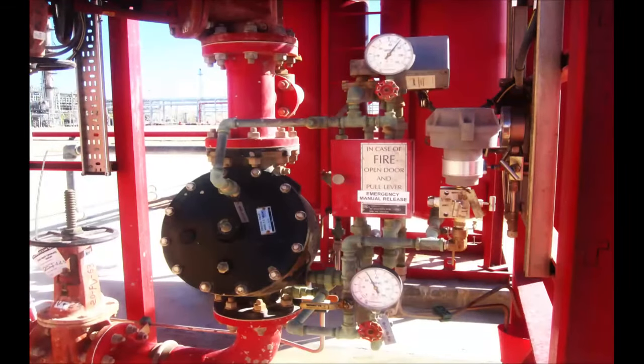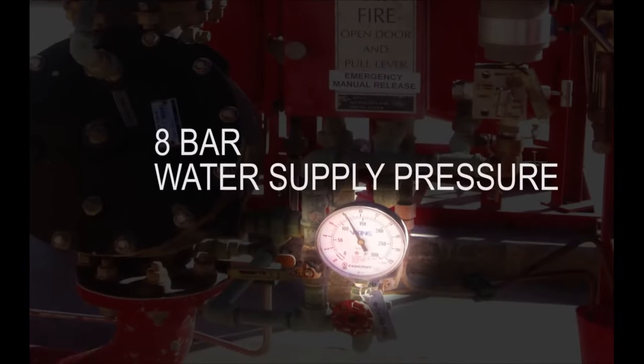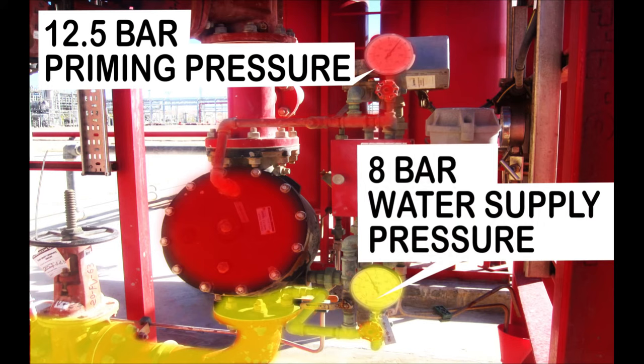This photo shows the deluge valve in the normally closed position, where the priming water pressure is 12.5 bar while the water supply pressure is 8 bar. The priming water pressure branches from the water supply pressure, so normally there should be zero differential pressure between them, which is essential for the deluge valve to remain closed. However, the priming chamber here indicates a higher pressure, which is common to all the deluge skids present on site. This could be explained due to the presence of a check valve before the priming chamber.